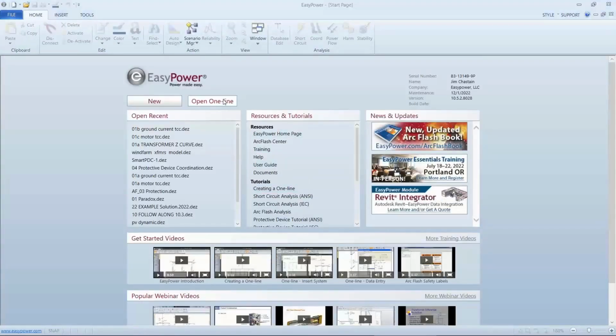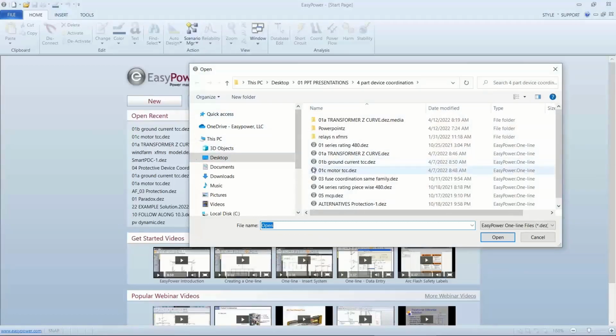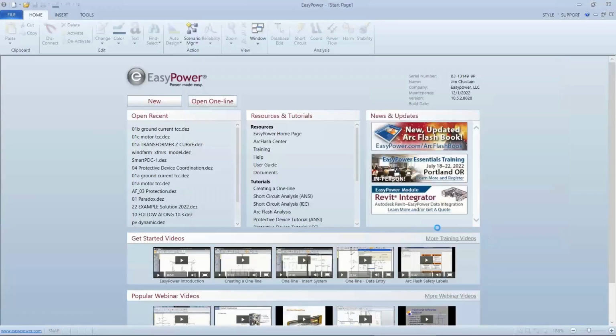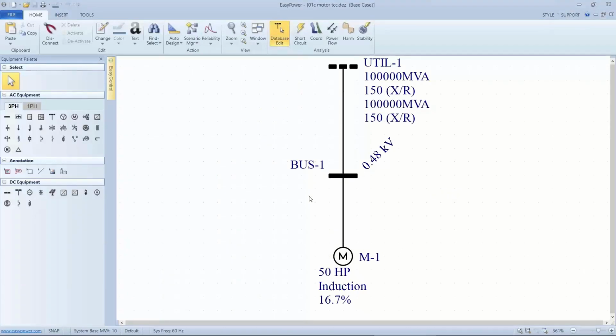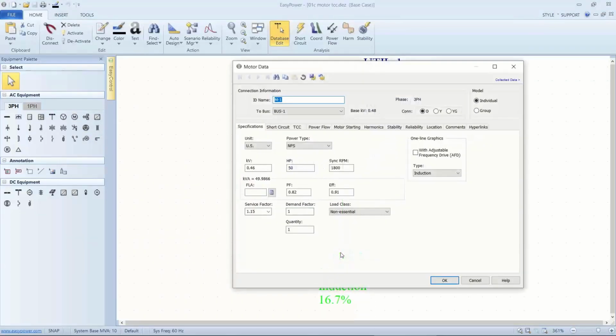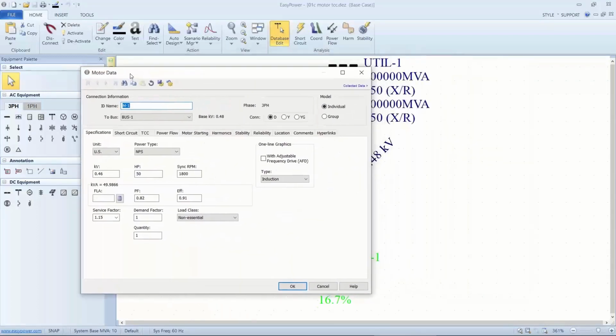So most of this information, well, again, the slides will be available on the website when we post the video. Most of this information is also on other webinars that we've done specific to motors and to protective devices. So again, in Database Edit, I've found the motor icon from the equipment palette and put it in my system, in this case 480 volts. If I open the dialog box for the motor, and again, there are times that I may want to actually take an image of the motor nameplate and save it. But the primary thing that the tool is looking for is horsepower.